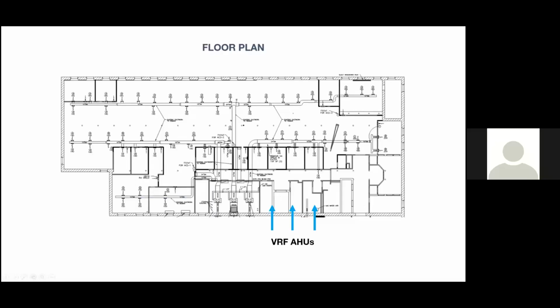Now, looking at the floor plan and showing a visual of the ductwork configuration, I'll just skim through this quick. You can see the large duct runs, which would mean there's a lot of static for the fans to push against. So this is why we could not just use any off-the-shelf VRF indoor unit that has that limit on the amount of static. So with these semi-custom air handlers, we can size the fans accordingly and ensure we can push the air through all that ductwork.